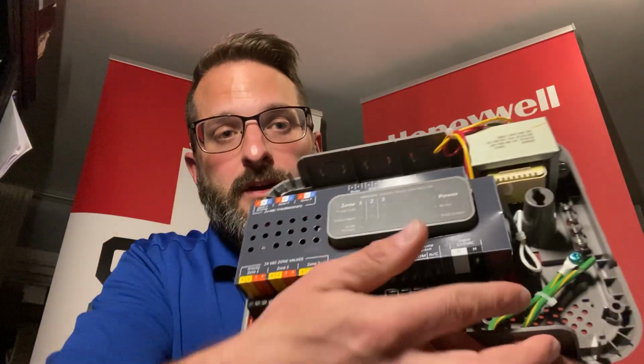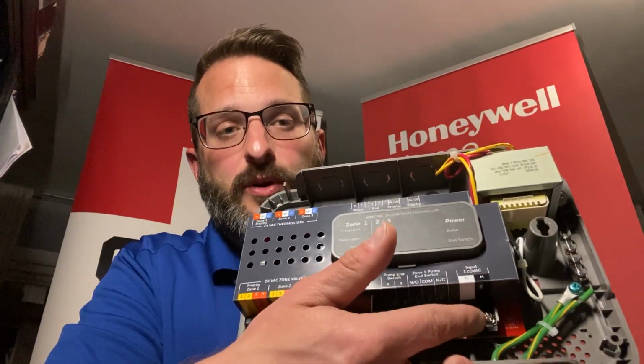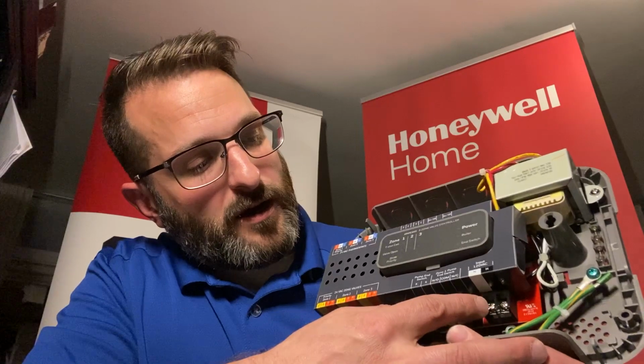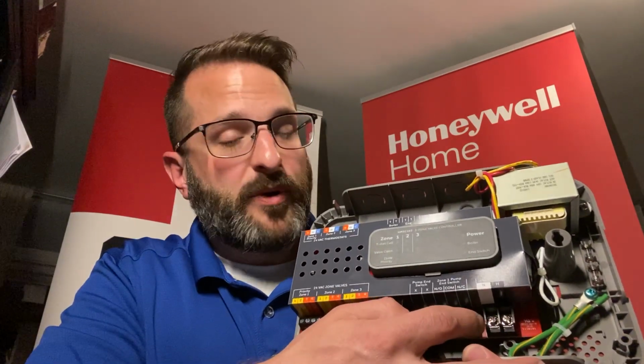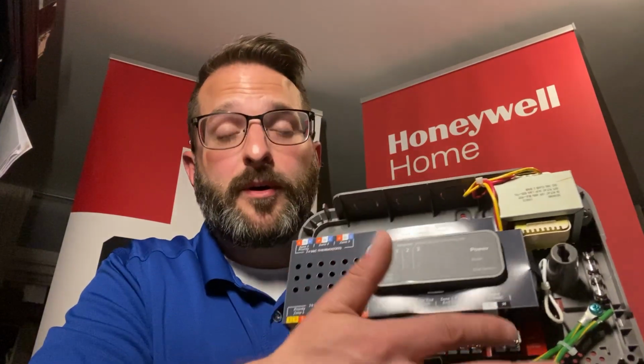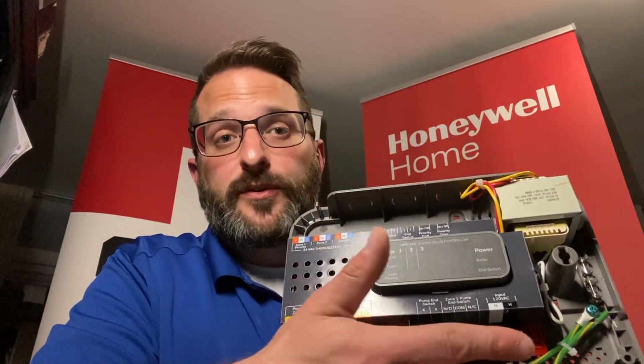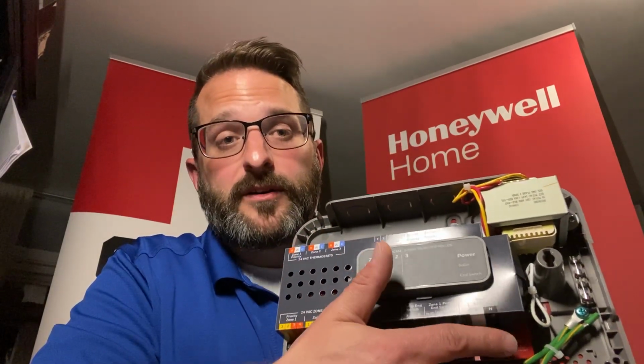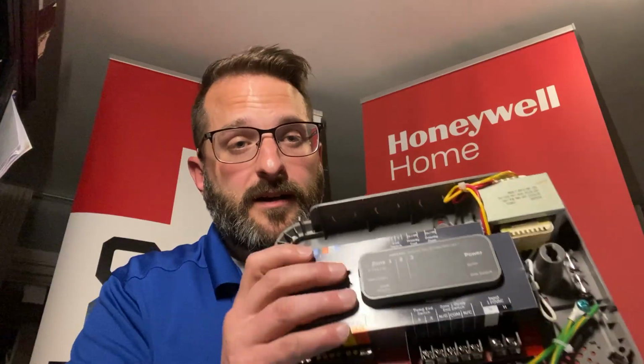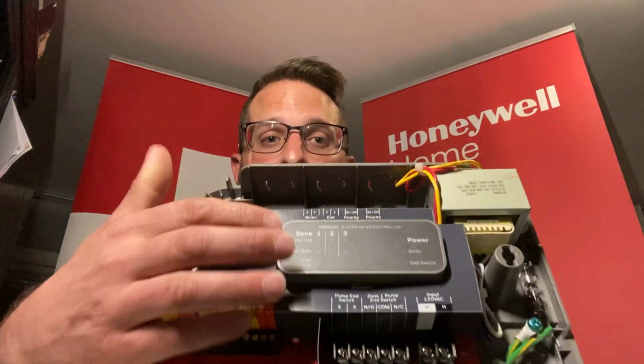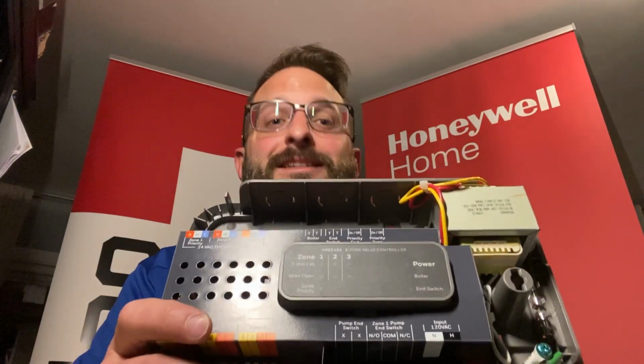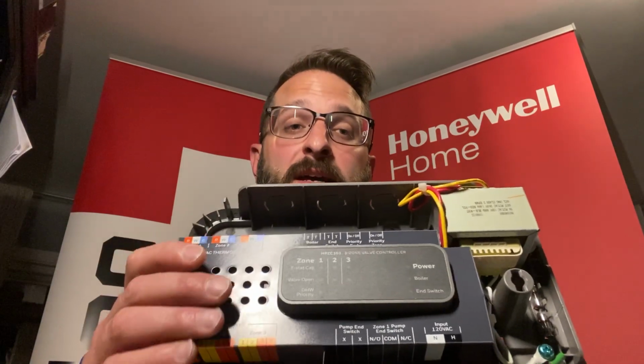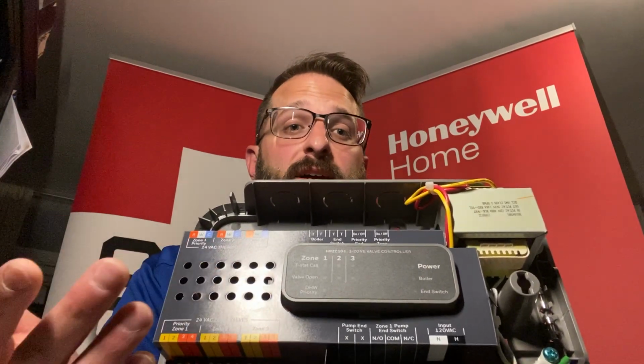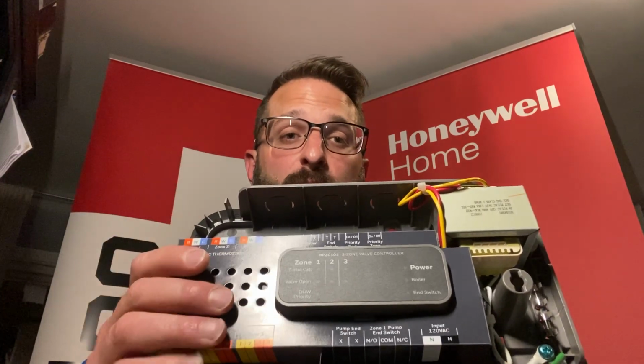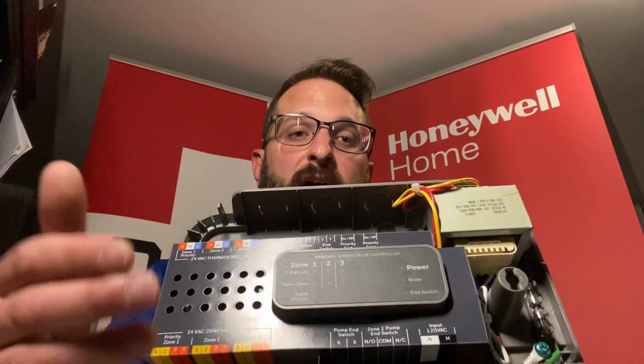So moving down, we have our 120 volt input for our power in. We have some dry contacts for a pump if you're going to be using a secondary pump, or if you're going to be pumping to an indirect water heater, you can add that onto here. And then I also want to note that the actual display stays with the panel when you take the cover off. Installers and service guys really like this because they can actually see what's going on, and they can see what's being called out as they're doing their troubleshooting.